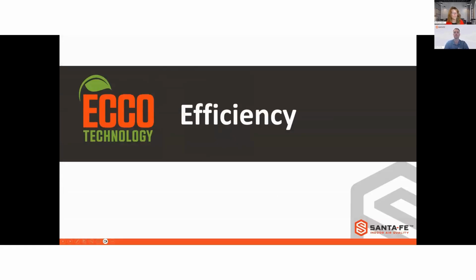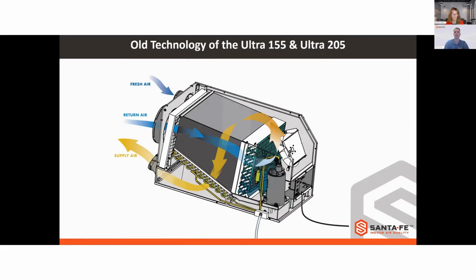So now we're going to jump into the new ECCO technology, the whole focus of which is efficiency. If you have been using our Ultra 155, 205 in the past, you might be familiar that these units had an air-to-air heat exchanger inside of them. What that allowed us to do is pre-cool the incoming air with air off of the evaporative coil, and we could get to dew point faster using less energy. So we would bring in the outdoor air and the return air, it would go through the evaporator, and you can see this path right here where we were pre-cooling this incoming air with the air that was leaving before it went to the condensing coil.